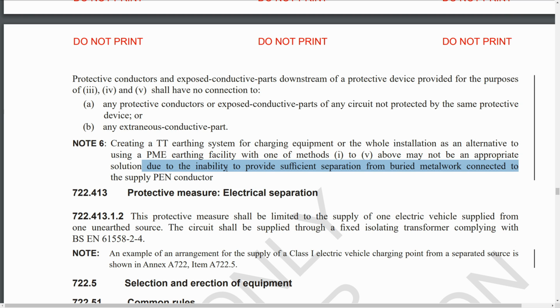Some network operators have specified things like 5 metres away as an absolute minimum, and this is already into the realms of big problems, because if you've got, say, the driveway in the front of a house, you can't realistically put an electrode in there and then say it's 5 metres away from all the incoming pipes, cables and whatever else, because 5 metres isn't exactly going to put you in next door's garden, and of course you can't go in next door's garden anyway because they've got gas pipes and water pipes and all the other stuff as well. So although in the past a lot of people have changed these things just to TT earthing and thought all is well, it all depends on where that electrode is going.